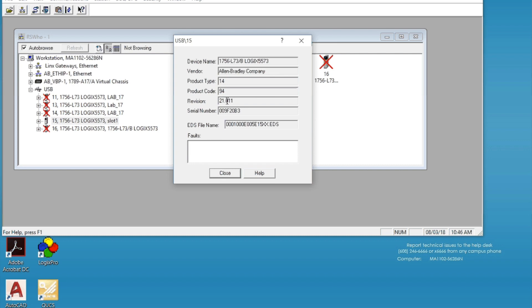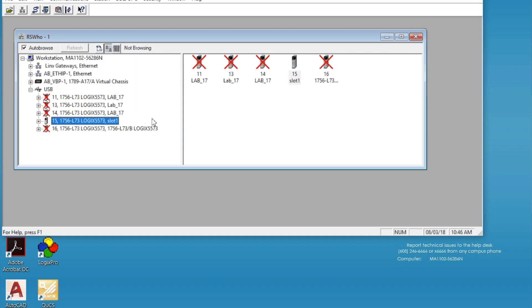And we want to update to version 30. So you have to have Studio 5000 version 30 installed or you must have downloaded the firmware package from the Rockwell website of version 30 to do this update. I'm going to stay connected and I'm going to open up the ControlFlash software.